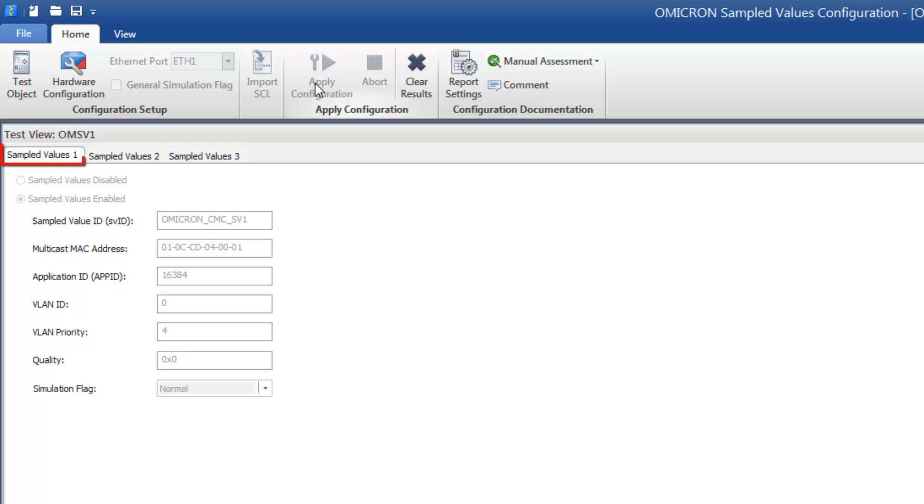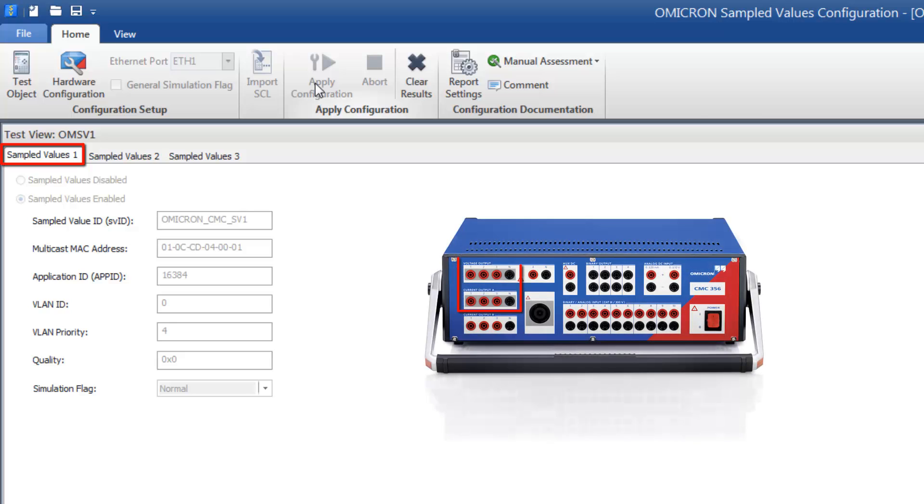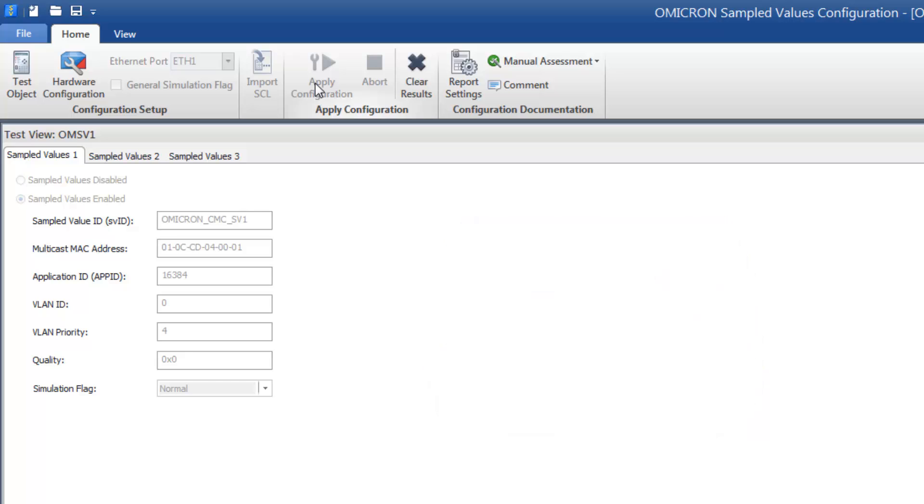The first sampled value stream corresponds to the first three current and voltage outputs of the CMC. The voltages or currents you generate here will be published as sampled values to the substation network, so you can use them as usual in all test modules.